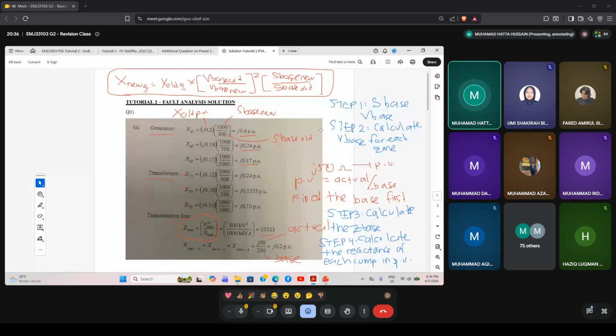You have to remember one thing, you have to remember the formula here. The new X for generator 1 equals the old X for generator 1 times the V base old divided by V base new squared, and then times the S base new divided by S base old. This is what you are learning from me.